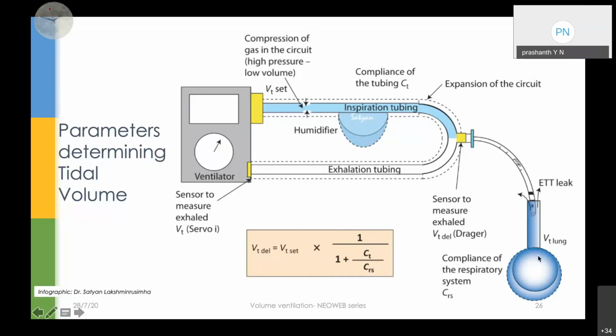So this figure is an important one to understand two things. One, how fallacious our volume control ventilation is when we are looking at the flows at the ventilator end. And what about this expansion of the circuit? We should be mindful of the compliance of the circuit as well as the ET tube leak. This figure also gives us a solution: if you have a flow sensor over here, measuring the volumes of air going in and coming out, this will closely approximate the tidal volumes.